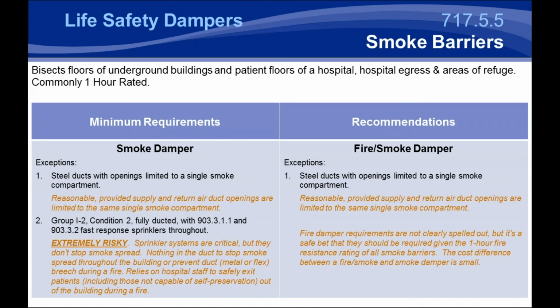And basically their argument was they've dealt with a lot of maintenance issues with dampers. Unfortunately, a lot of their maintenance issues really stemmed from fire dampers, not smoke dampers, and dealt with smoke dampers that were installed quite some time ago that were allowed to be shipped without actuators from the factory. Most of their rationale for removing the smoke damper requirement was that the dampers were installed incorrectly and never fully opened or closed. And that was basically because smoke dampers could previously be installed without actuators, with actuators installed after the fact by contractors when there was building power to operate these dampers.